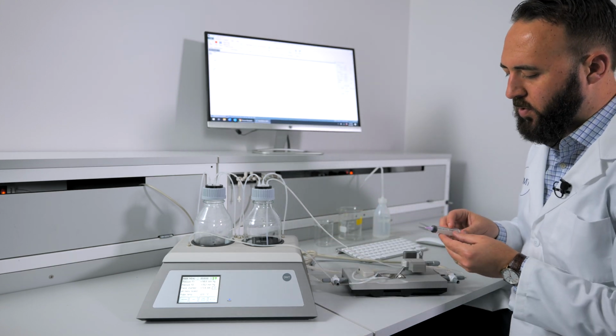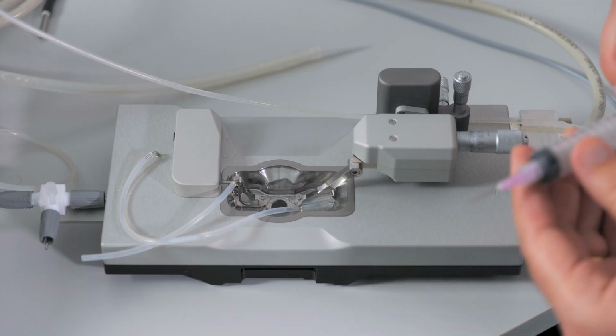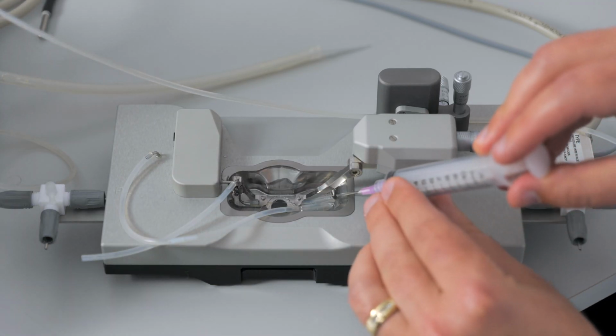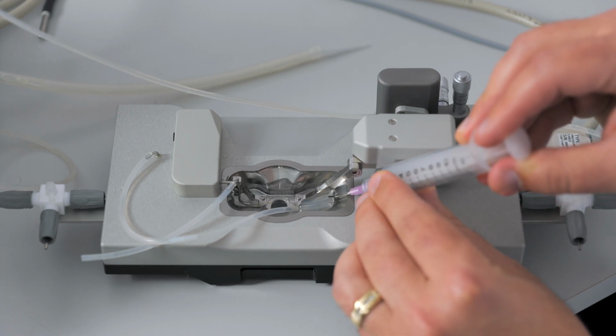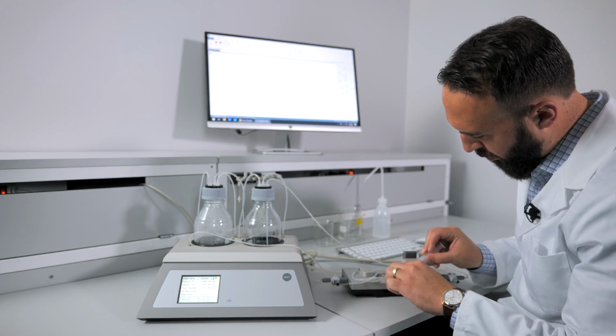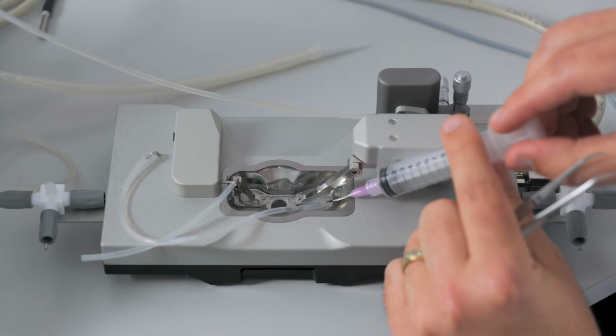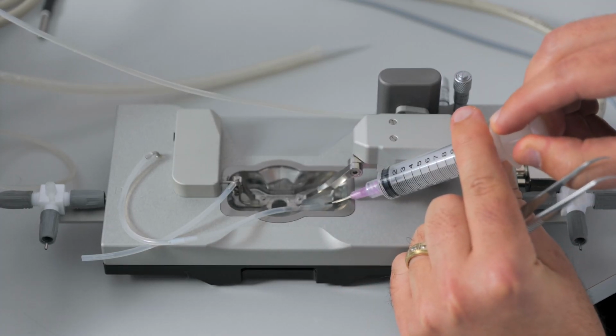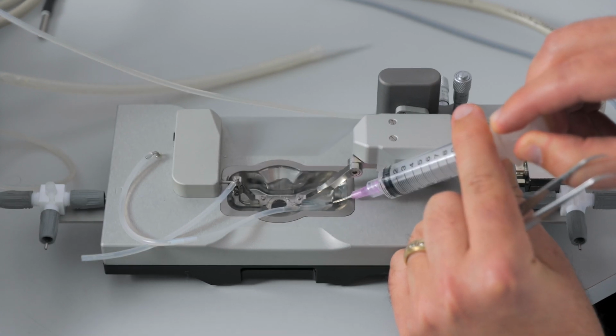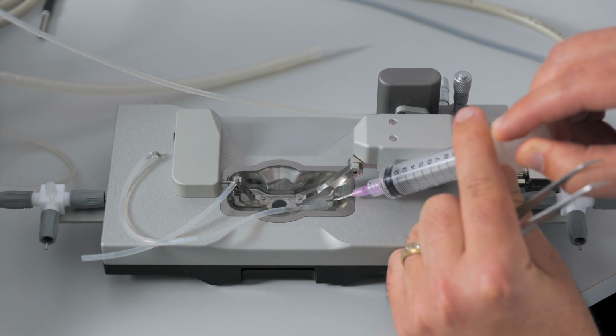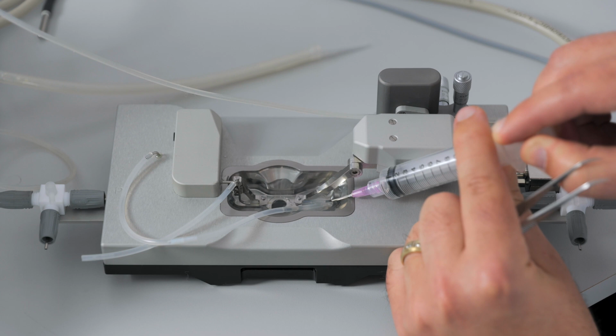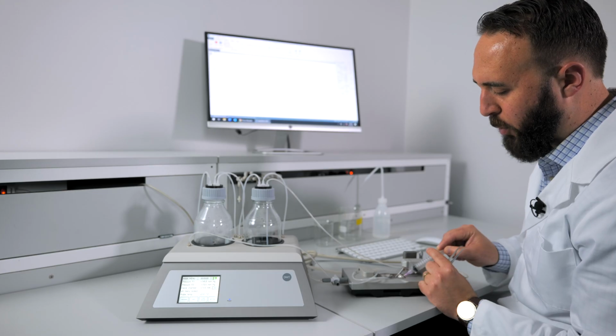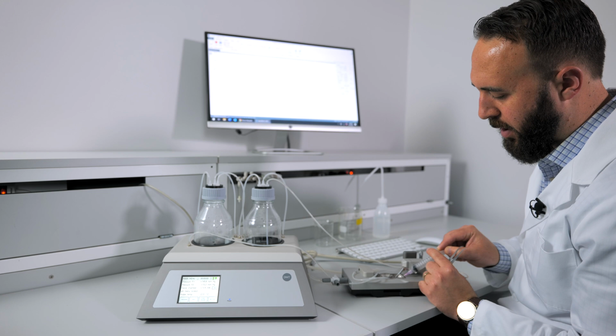You will use a syringe with a blunt 18 gauge needle tip, and you can connect it to the back side of the P1 tubing. You will then draw 2 to 5 mils of water back into the syringe. By drawing water back through the syringe, you are less likely to clog the tip of the cannula. You are not going through the pressure transducer, so you do not have to worry about how much pressure you are adding at this time.